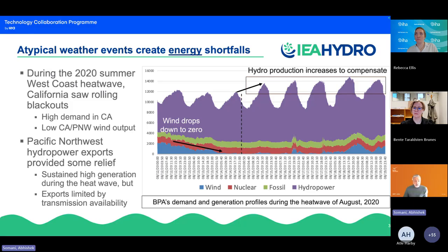A couple of things happened simultaneously. First, wind output just dropped down to zero right at the outset of the event. Wind speeds are weather dependent, so above average or below average temperatures can impact wind speeds and lead to changes in output. That's what we saw here: wind output dropped to zero. So that was a double whammy—increased loads and almost zero wind, from almost 2,000 megawatts down to zero.